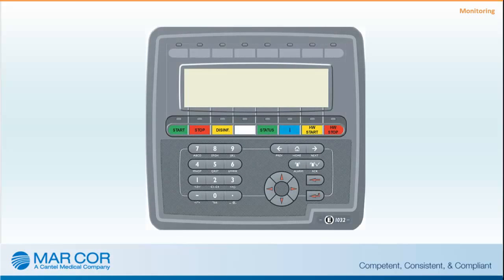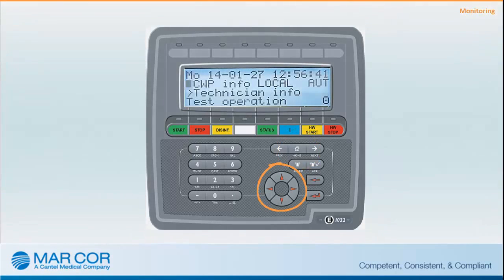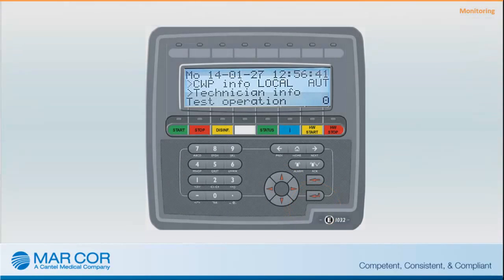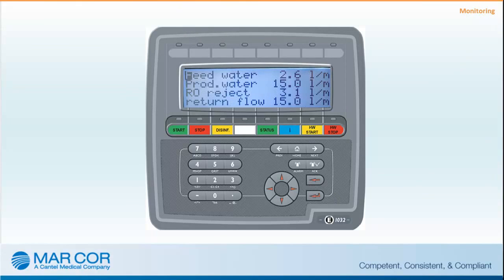The CWP RO parameters should be checked and recorded daily to ensure proper operation; the RO must be in operation when recording these parameters. To access monitoring information, press the Home Menu button. Move the cursor until it's flashing on the line that reads CWP Info, then press Enter to access the CWP Info screen. Use the up and down arrows to scroll through the parameters, which include: inlet water flow rate, product water flow rate, RO reject flow rate, and return water flow rate.